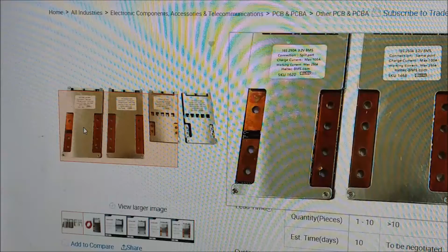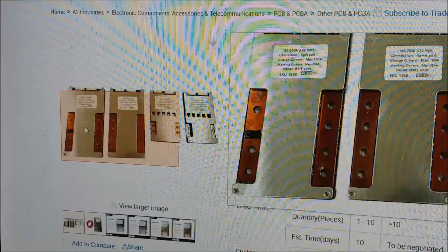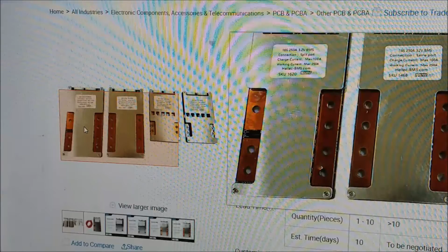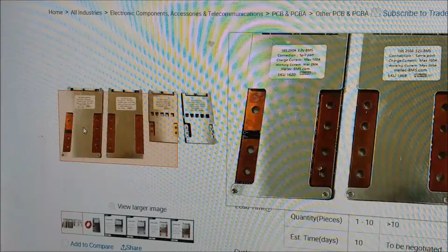It'll instantly come to temperature, and you can solder it pretty quick, a few seconds. If you try to heat that up with an electric soldering iron, you'll probably wreck the board and void the warranty. Plus the holes in the board aren't big enough for the bolt size needed for a cable lug. So what they did was make it so you bolt your terminal lugs to the copper. You through-bolt it, and you can put one on either side, as long as you've got a good contact patch.